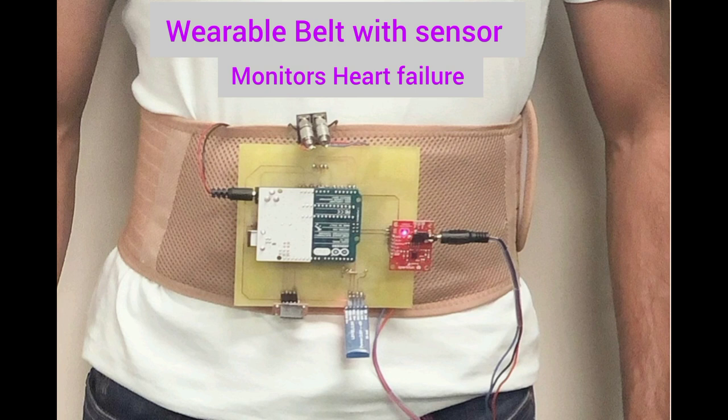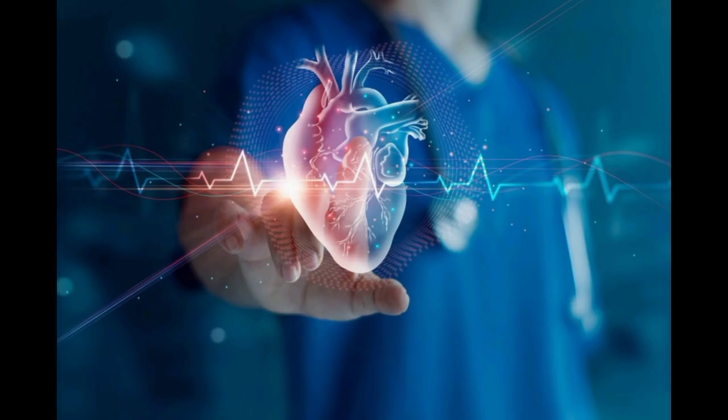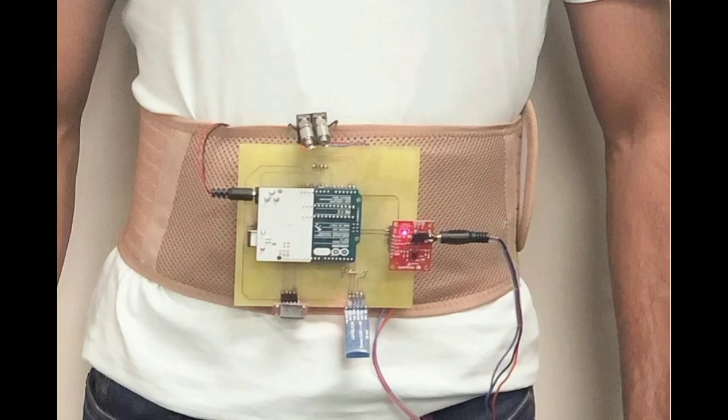sitting, standing, lying down, and walking. For each condition, results were obtained for each of the sensors sequentially. The physiological parameters selected are significant in determining heart failure symptoms. Findings showed that all of the sensors kept track of the changes for all of the different conditions. So the position sensor correctly highlighted the change in position in different conditions and could be used to identify different states of the wearer of the device. In addition, the heart rate sensor continuously kept track of the heart rate. Importantly, the device correctly highlighted minute changes in thoracic impedance.